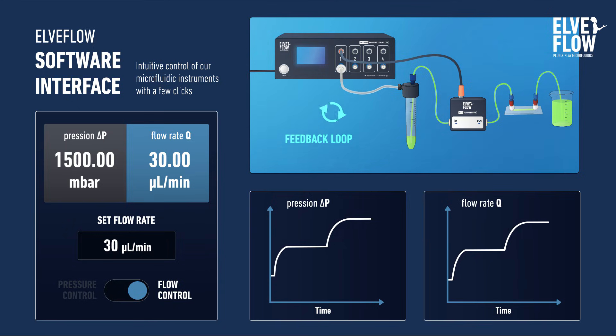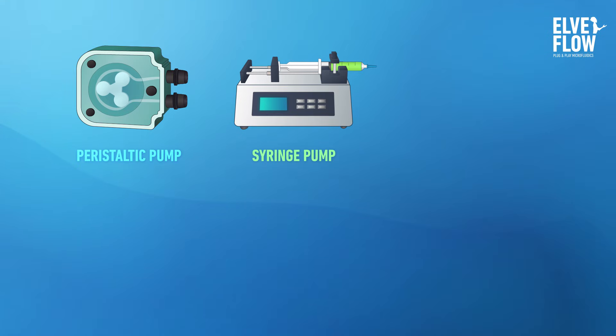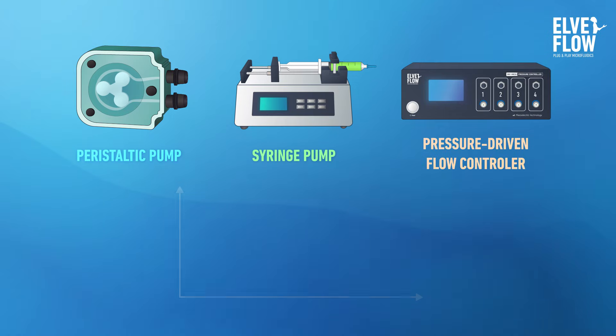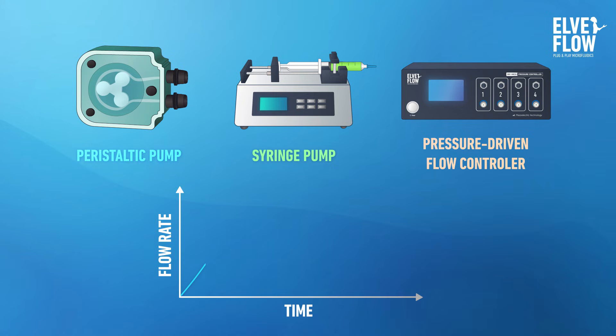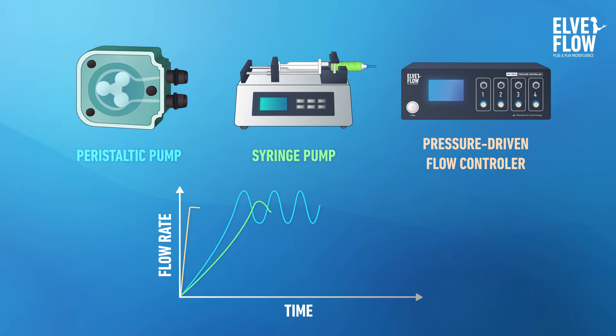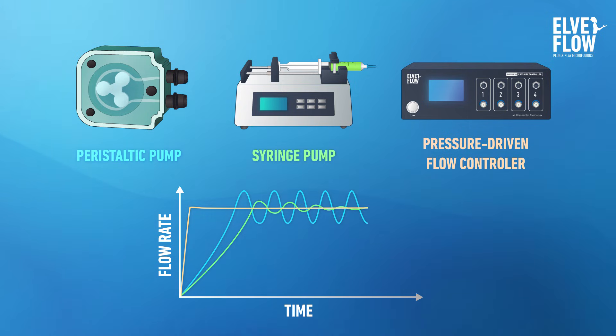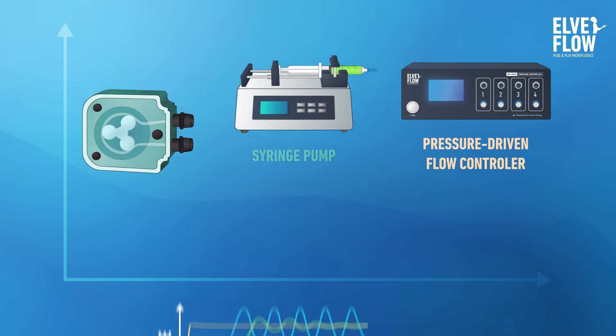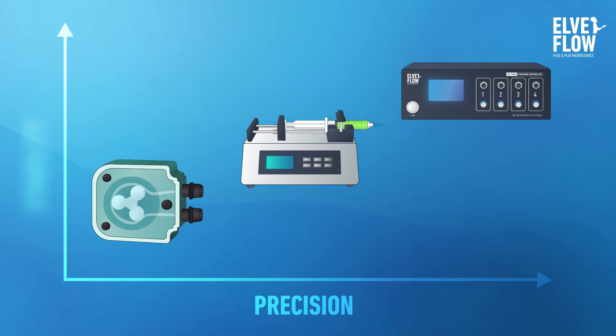Both peristaltic and syringe pumps are easy to use — they push liquids by a mechanical action. Yet this mechanical movement creates bumps and pulses, limiting performances in terms of response time and flow stability. In a pressure-driven flow control system, the liquid is pushed by a gas in a smoother action, leading to a pulseless flow and a higher flow control accuracy.